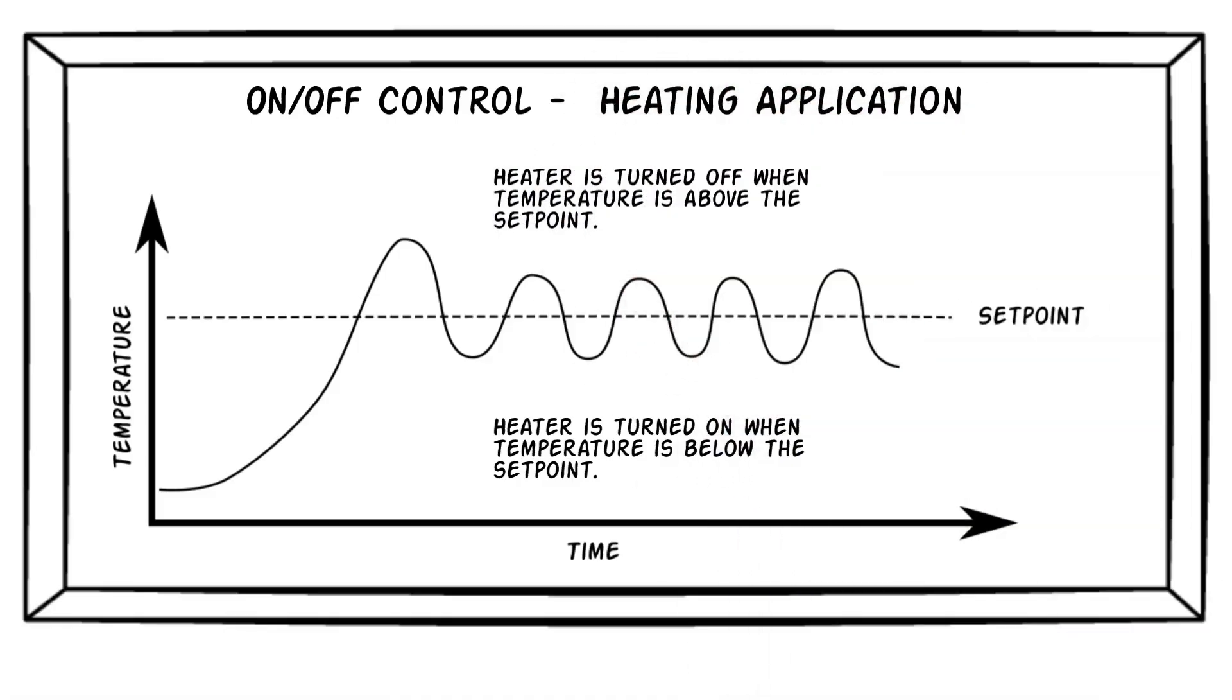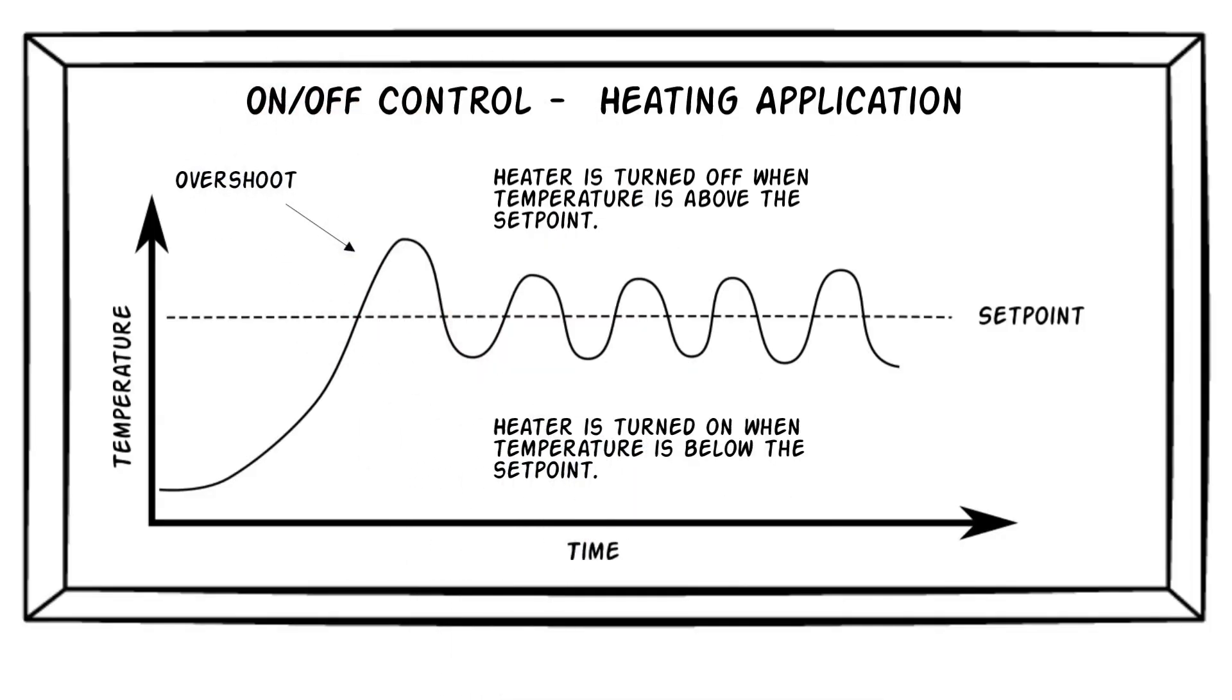This is a very simple type of control, but it tends to result in overshoot, in which the temperature initially overshoots the set point. After the overshoot, the temperature will normally settle around the set point, but with oscillations that fluctuate above and below the set point.